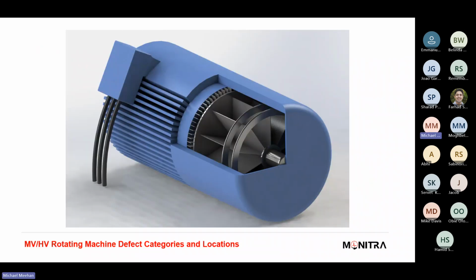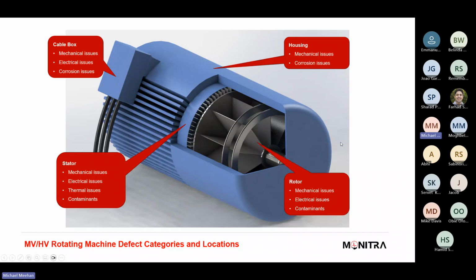So when we think of a machine, obviously this is a very simple pictorial, but some of the key features and key areas of a machine that we look at where there's potential failure modes. Obviously stator is one of the primary ones. I spoke about that quite a bit. You get the mechanical, you get those thermal stresses, which are quite prevalent across the stator. You do get cable box issues.